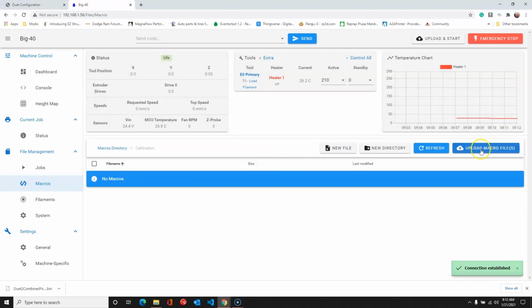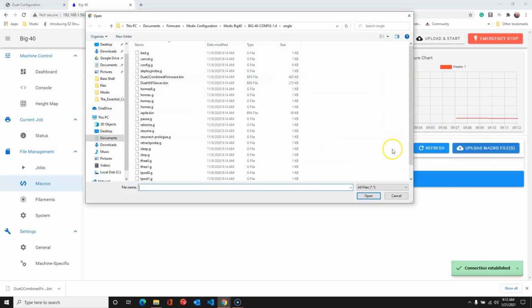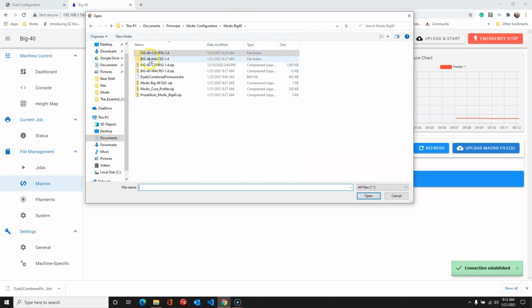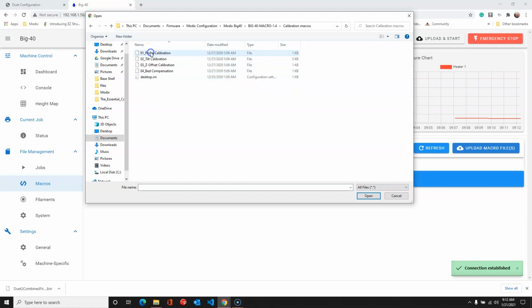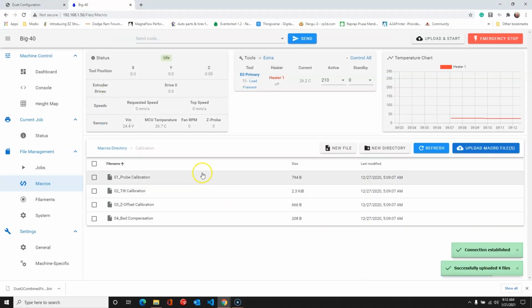We're going to select the button that states Upload Macro Files, go back into our file structure, look for our macro download, and go into Calibration Macros. Select those 4 files. In the calibration folder here, you're uploading them into the calibration folder on your Modix. Select Open, and we now have these 4 in the correct folder.